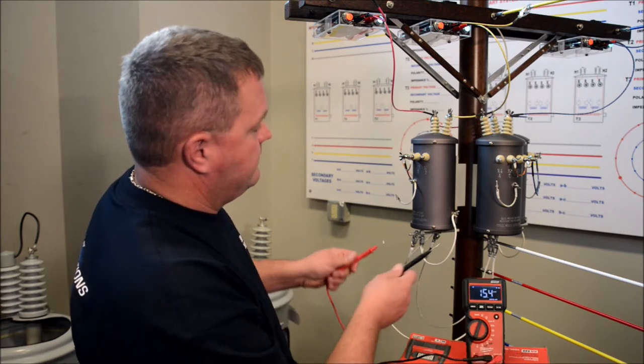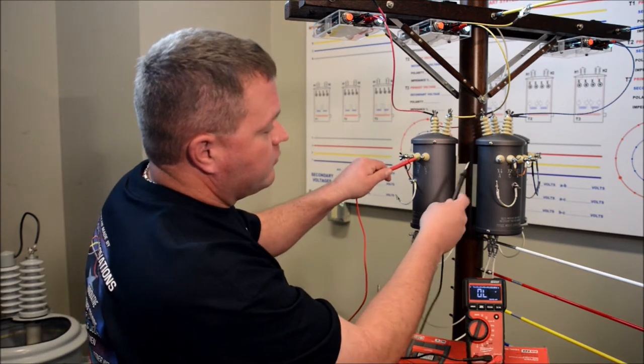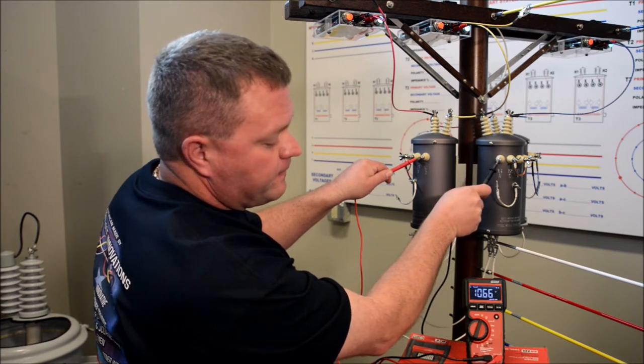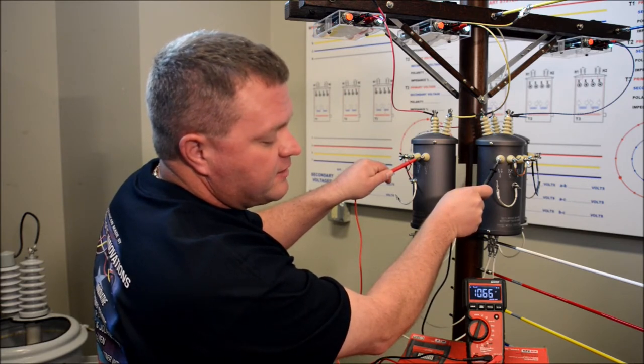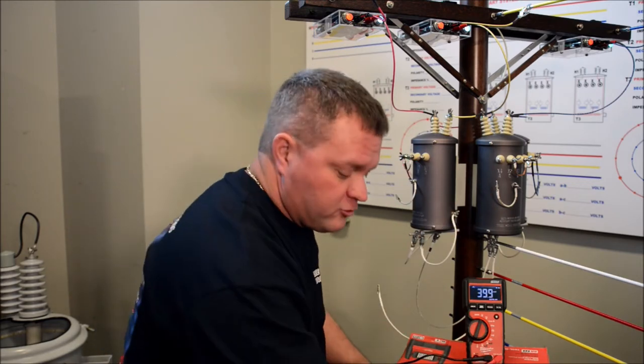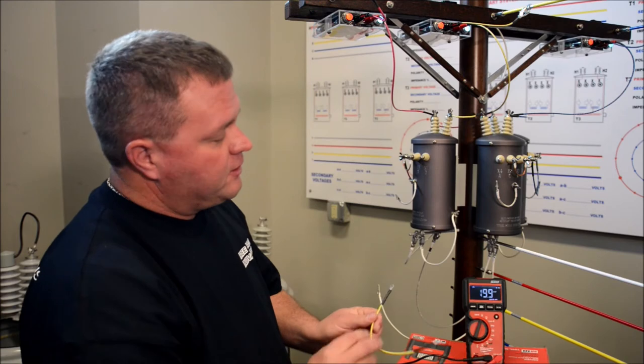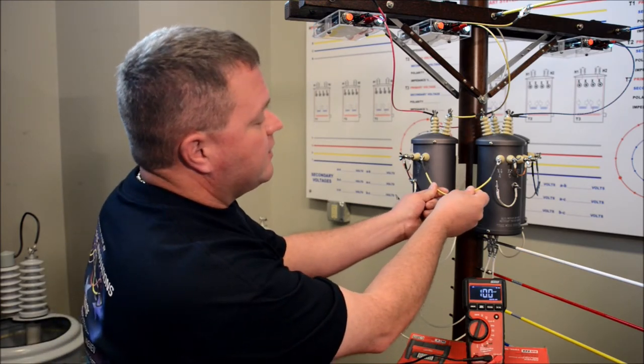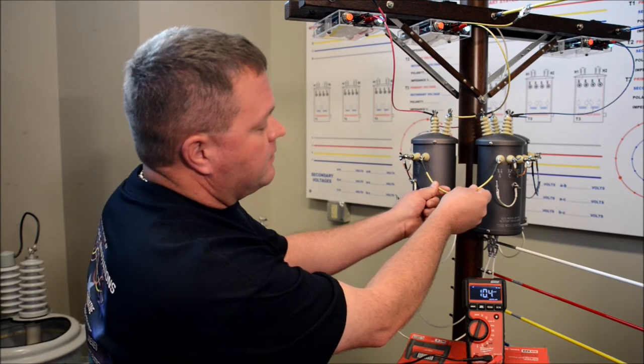We're going from X1 to X4 or X1 to X3 depending on what style of transformer you're using. We're getting approximately 10.6 volts, which would be good. I'll show you the same thing we did up there. Insulated wire. We know this is good. Before we touch them together, we can now complete the circuit. This is good.